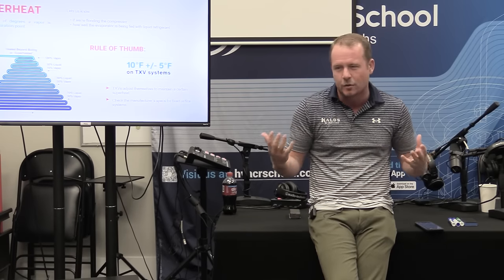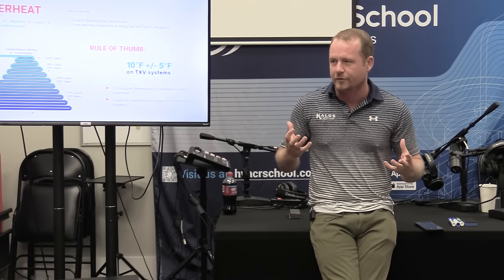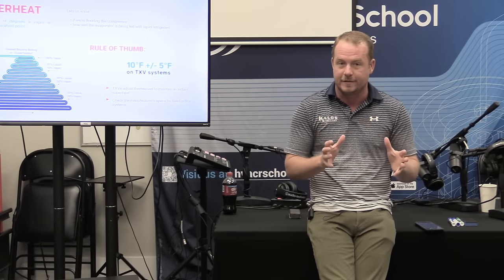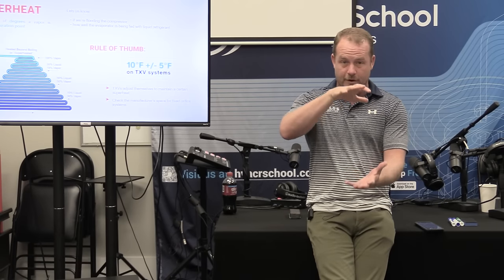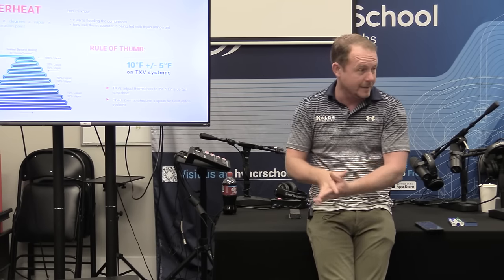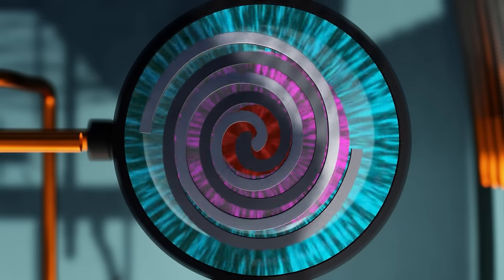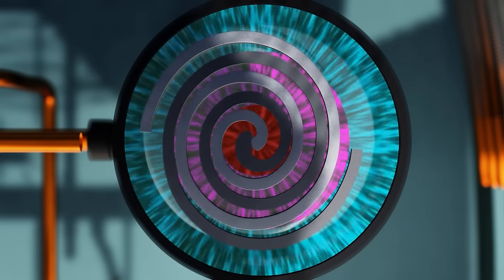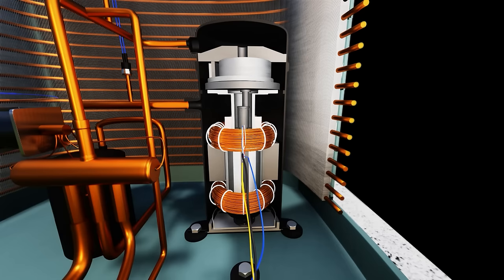If there's lower pressure, that suction gas is lighter — and we know what should be in the lines: only refrigerant. No air, no moisture, no nitrogen, no other refrigerants. Things get really crazy when we have stuff in the system that's not the refrigerant we think it is. But so long as there's all refrigerant in there, if we have less pressure, the molecules are more separated — we're pushing on them less, meaning they're lighter. Lower suction pressure means lighter gas going back to the compressor. With every stroke of that compressor or every oscillation of that scroll, it moves less, because while it's moving the same volume, each volume has less mass. Lower suction pressure means you're moving less refrigerant.